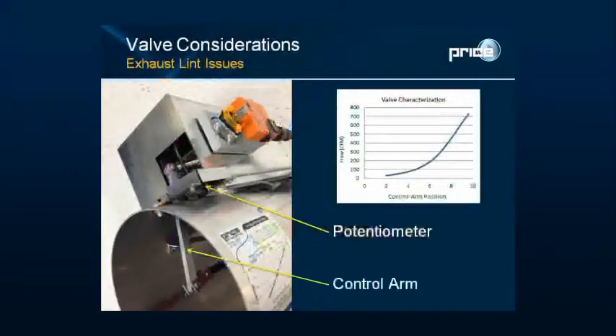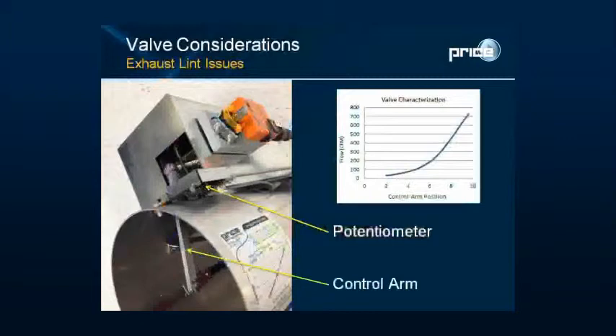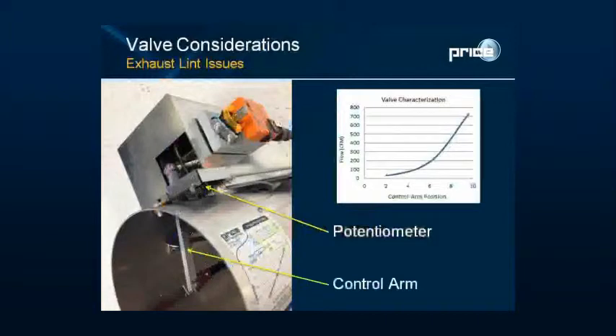Instead of an airflow sensor, the Venturi valve is factory characterized. A potentiometer attached to the valve measures the position of the control arm, which adjusts the position of the center shaft carrying the engineered cone and spring assembly. Because the valve is mechanically pressure independent, we can directly relate the control arm position — expressed as a 2 to 10 volt output — to flow through the valve, without needing to know the exact pressure across it, provided a minimum pressure is maintained. This allows flow control without a flow sensor.